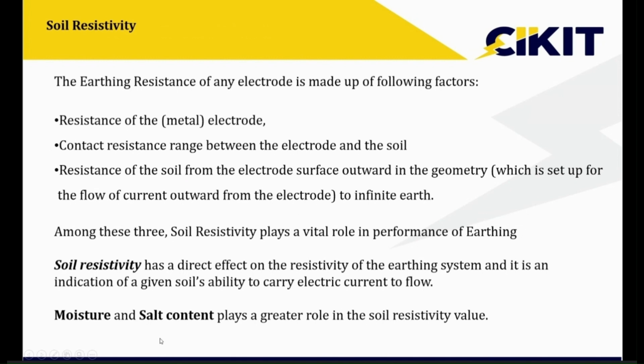As I mentioned, the soil resistance mainly depends upon the soil resistivity, and the soil resistivity mainly depends upon the moisture and the salt content. If the soil has more moisture, the soil resistivity will be lesser. If the soil has more salt content, the soil resistivity will also be lesser. That is the reason you don't measure soil resistivity during rainy conditions: the moisture content will be higher, and the value we measure will always be lower than the actual value. So all measurements should be carried out in dry conditions, not rainy conditions.